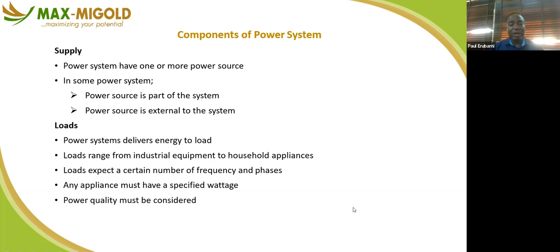Any appliance must have a specific wattage. When we talk of wattage, we are talking of power, the power rating. Like your AC, they'll say 2 horsepower, 1 horsepower, 1.5 horsepower. So they are rated in specific wattage, so that when you are loading your generator or procuring equipment in terms of power distribution, you know exactly what you are producing. If you procure underrated equipment, it will affect that equipment. So you need to know the rating of your appliances before you order any generator or whatever you require to power your system.